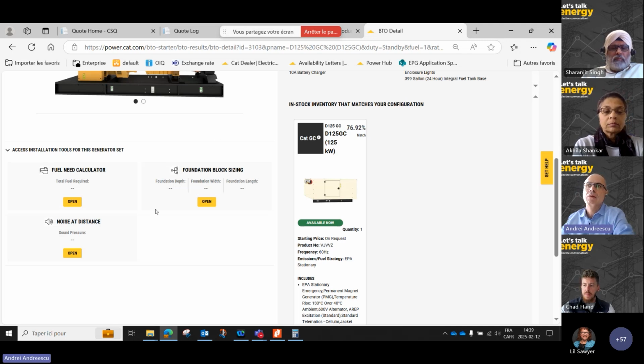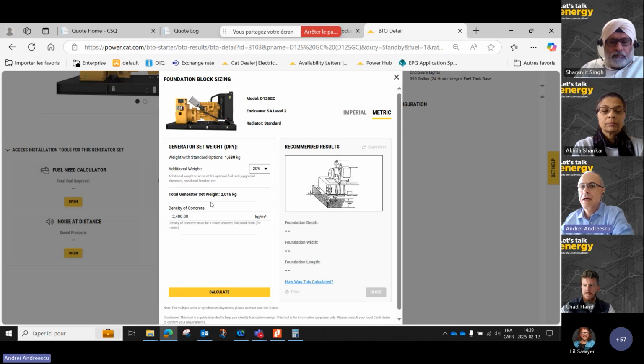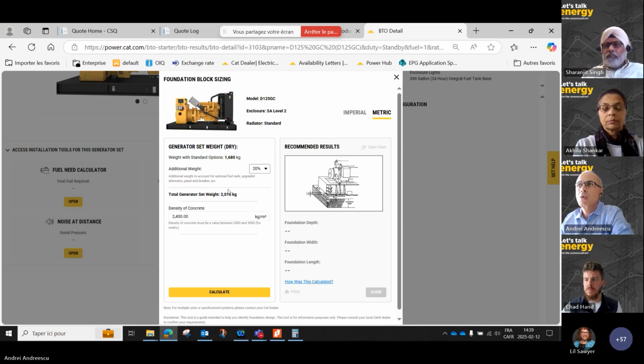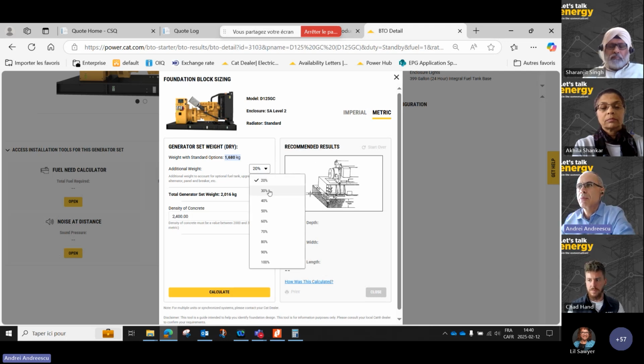Last but not least, we have a third tool that calculates the dimensions of the concrete foundation. We start from the weight of the generator set with the enclosure - the tool tells us that weight. There is provision for additional weight, which may be, for instance, the weight of the fuel inside the tank, and we can add that as a percentage.